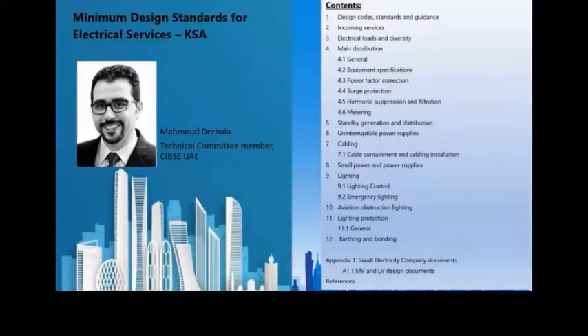Chapter 7 is for cabling, and this chapter aims to cover the SEC requirements, which lean back on DBS 09 and DBS 10, SDMS 03, showing the 13.8 kV and 33 kV medium voltage cable sizes recommended by SEC, and the maximum firm capacity of each cable.